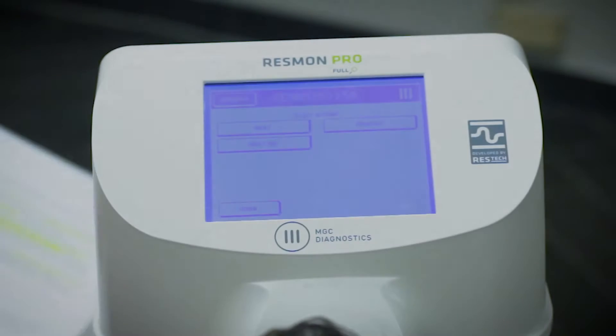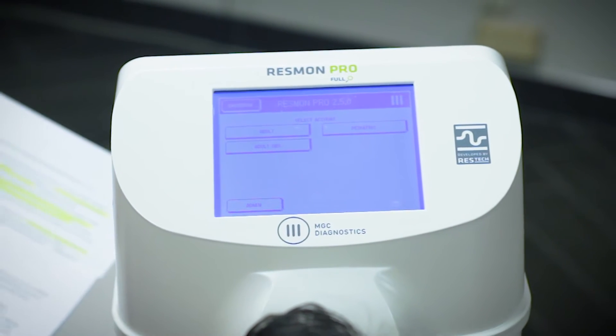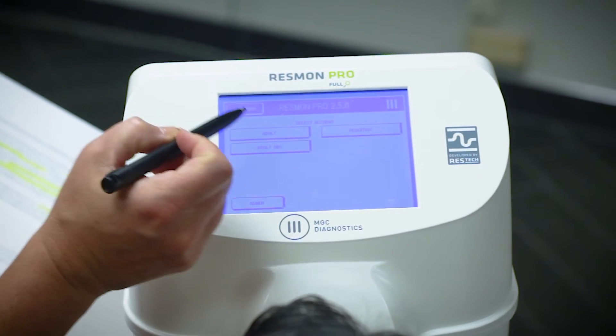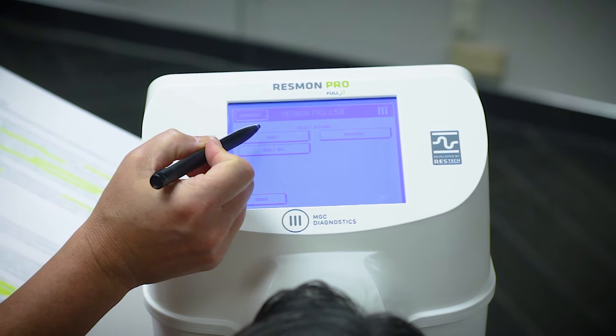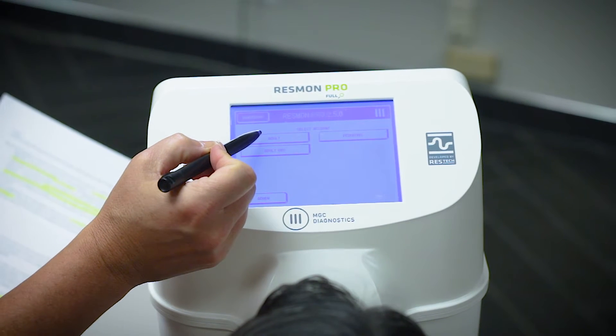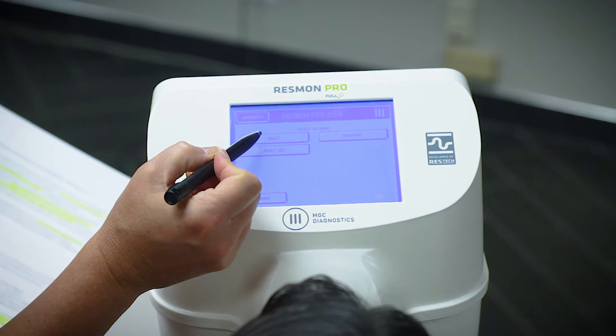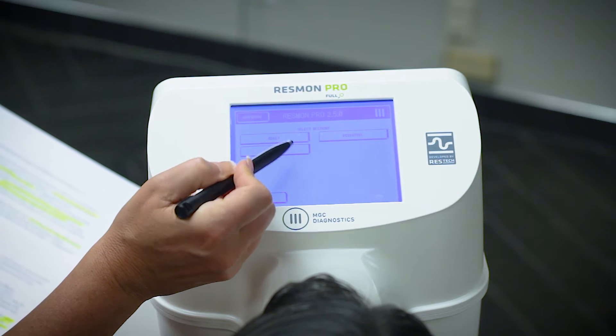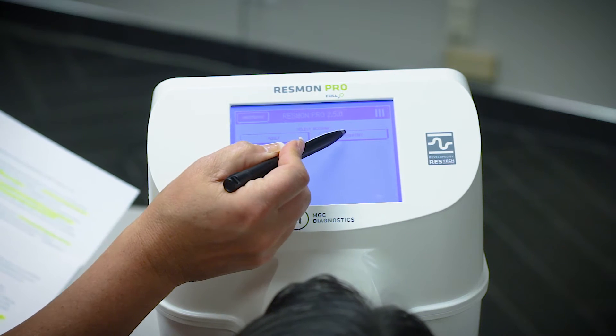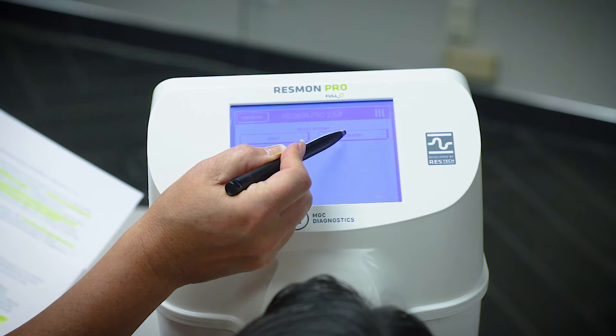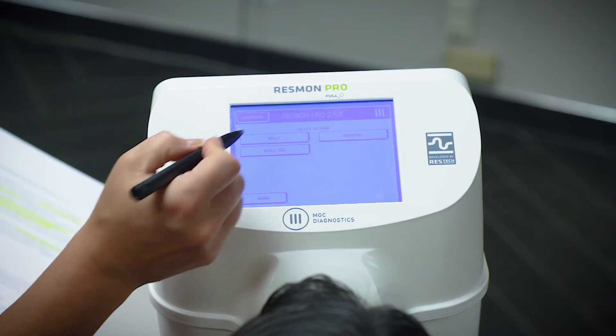Let's begin testing using the Resmon Pro. The user can program accounts, perhaps one per type of disease, doctor, or study. What we have is one for adult, adult obstructed, and pediatric with different frequencies.